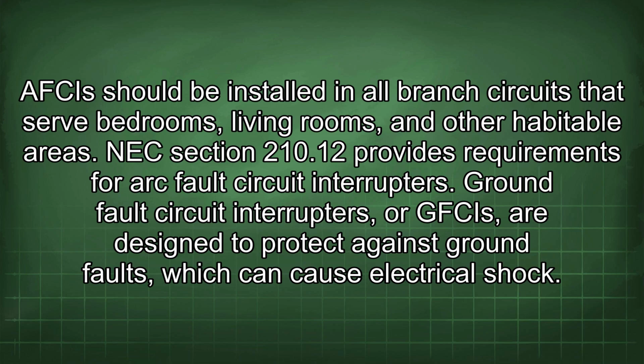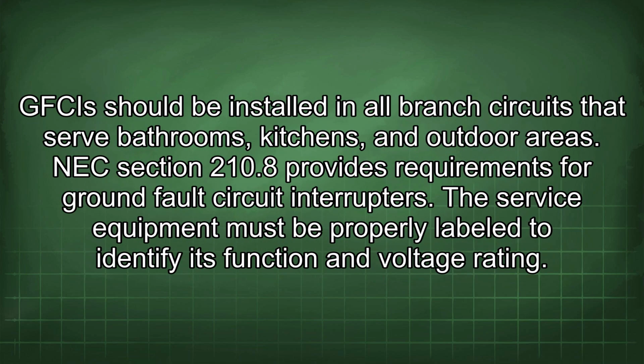Ground fault circuit interrupters, or GFCIs, are designed to protect against ground faults, which can cause electrical shock. GFCIs should be installed in all branch circuits that serve bathrooms, kitchens, and outdoor areas. NEC Section 210.8 provides requirements for ground fault circuit interrupters.